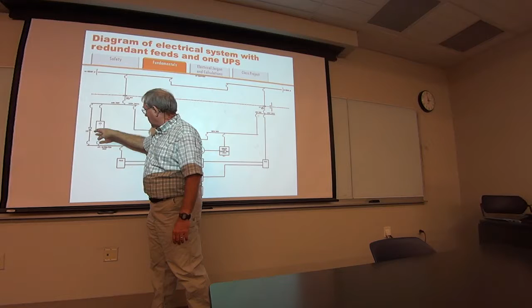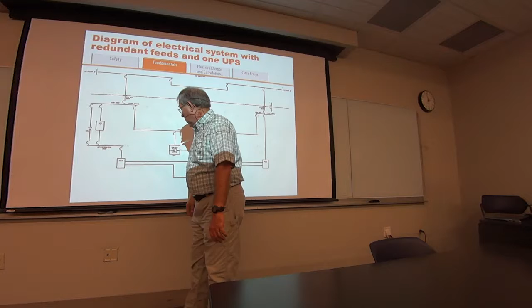Now here, I put a UPS on this side. Here's the UPS. This is static bypass because you have to have this so you can cut this off and work on it. And actually, in all reality, this will be inside this box, so you'll have a physical breaker bypass in it called a maintenance bypass, okay?